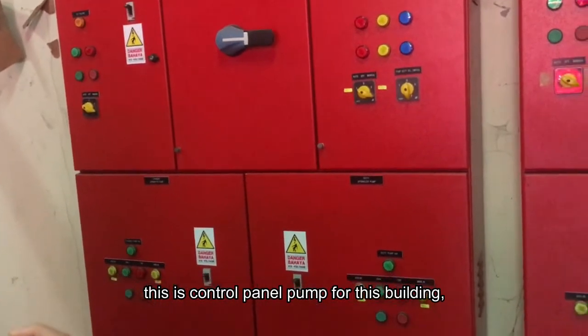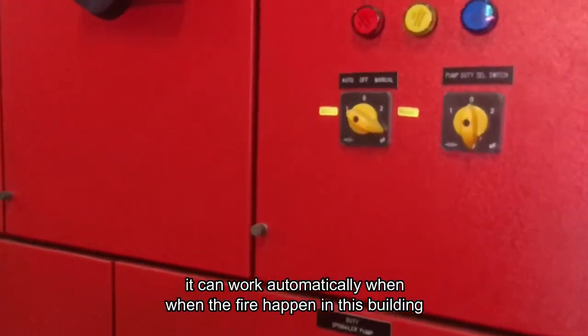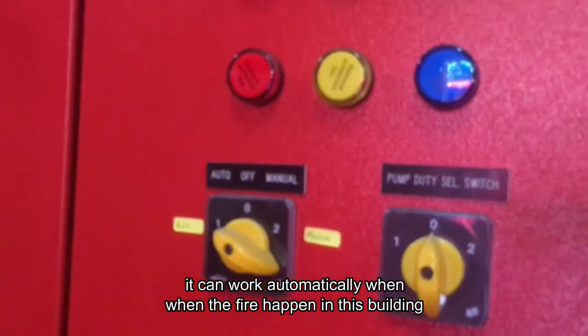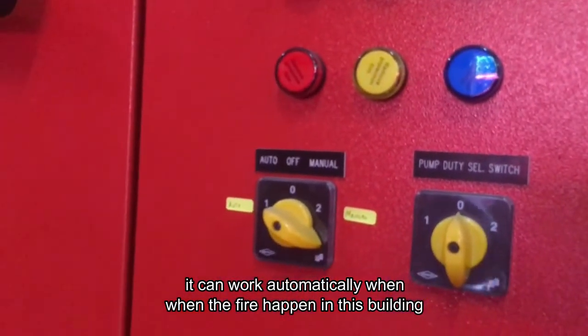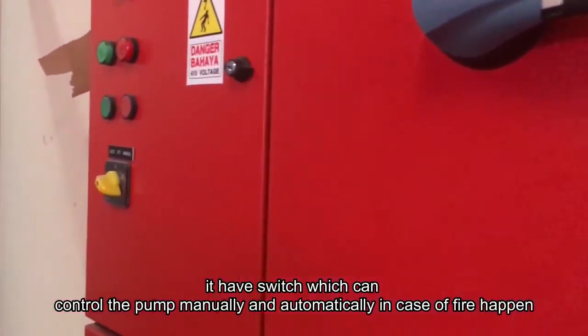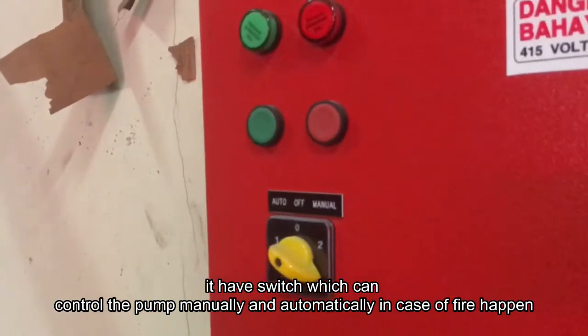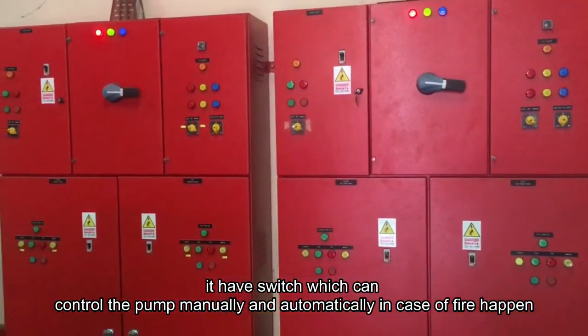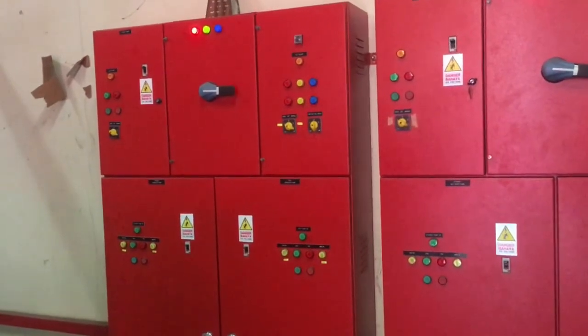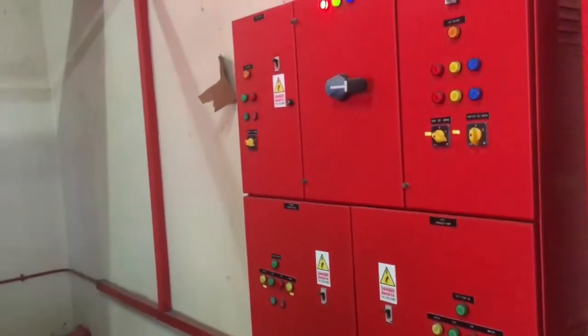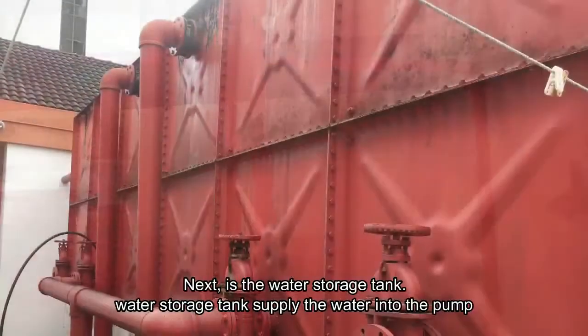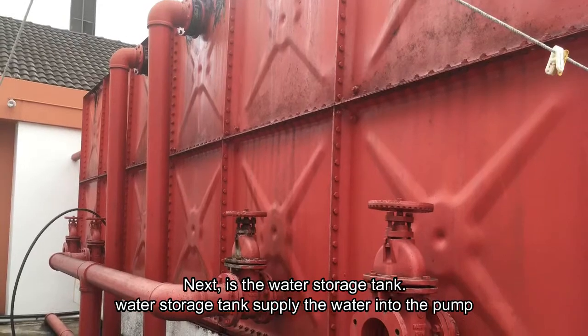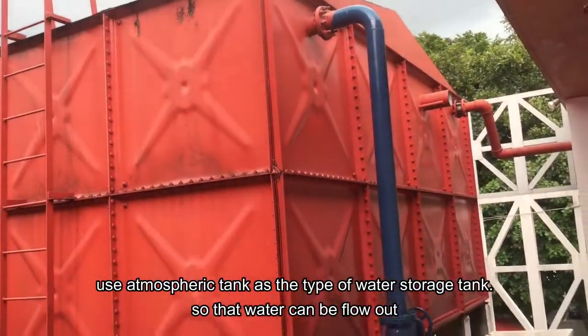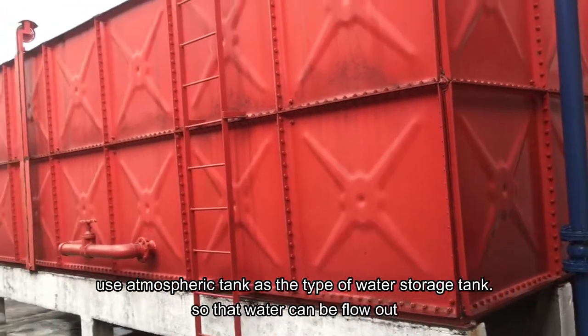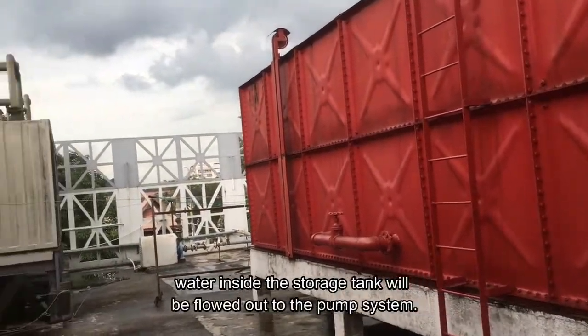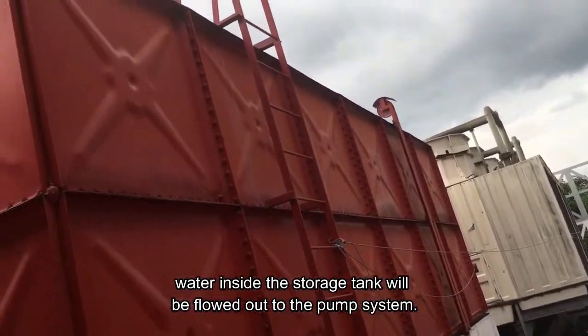This is the control panel pump for this building. It can work automatically when fire happens in this building. It has a switch which can control the pump manually and automatically in case of fire. Next is the water storage tank. The water storage tank supplies water into the pump. It uses an atmospheric tank as the type of water storage tank so that water can flow out. Water inside the tank will flow out to the pump system.